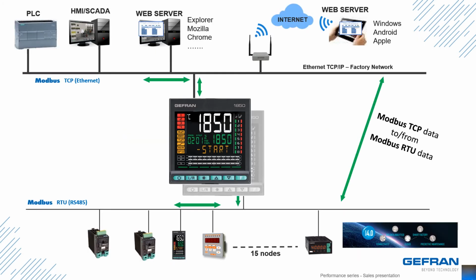In this diagram, on the top, I'm showing a Modbus TCP Ethernet connection to a PLC, HMI, and the Internet, also a web server too. On the Modbus RTU, on the bottom, I'm connected up to 15 nodes. Then if I have a bridge, I can move the data from the Modbus RTU to the Modbus TCP. If you want to know the current or voltage on a Gefran power controller and report it to your SCADA system, it can be done using a Performance series controller as a bridge.